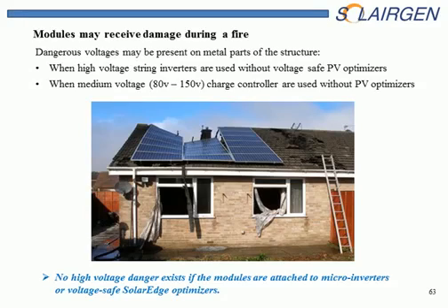If it's microinverters, not a big deal, nothing to worry about. If it's PV optimizers that are voltage safe, not a problem. If it's the old string inverters, or if it's a battery system with charge controllers, then the voltage could be somewhere between 80 to 500 volts. And so that's something to be very cautious of as you approach.